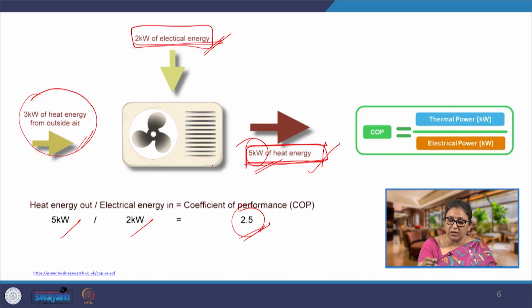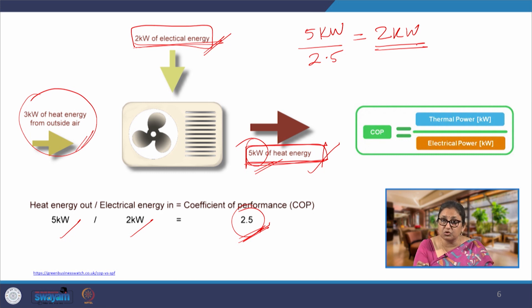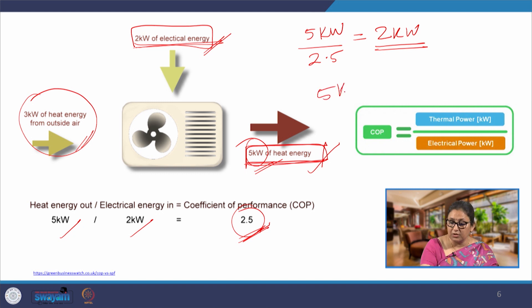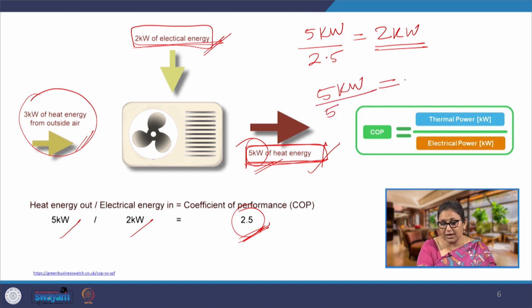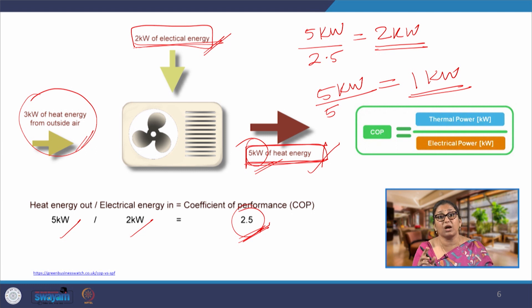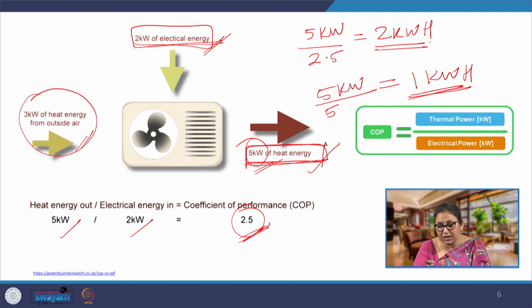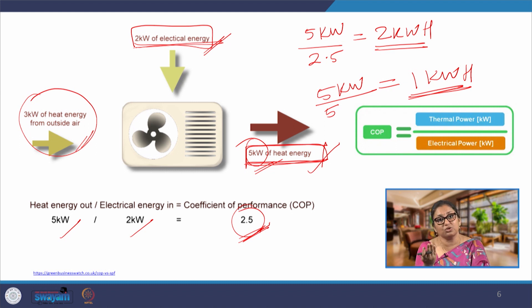If the same work is to be done — removing 5 kW of heat — with a system of COP 2.5, electrical energy consumption is 2 kW. Compare this with another system of COP 5: electrical energy consumption drops to 1 kW. We also need to know for how many hours the system is running. Assuming one hour of operation, the first system consumes 2 kWh and the second 1 kWh. Doubling the COP reduces electrical energy consumption by half.